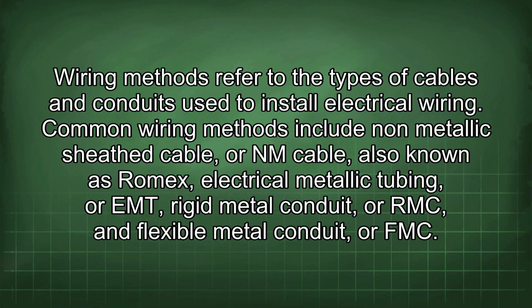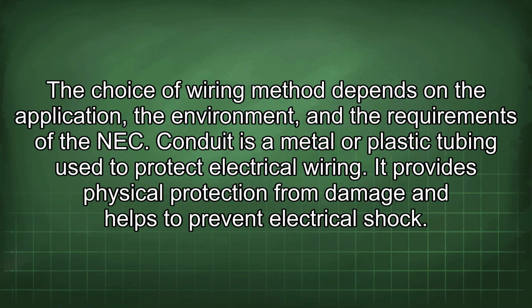Wiring methods refer to the types of cables and conduits used to install electrical wiring. Common wiring methods include non-metallic sheath cable, or NM cable, also known as Romex, electrical metallic tubing, or EMT, rigid metal conduit, or RMC, and flexible metal conduit, or FMC. The choice of wiring method depends on the application, the environment, and the requirements of the NEC.